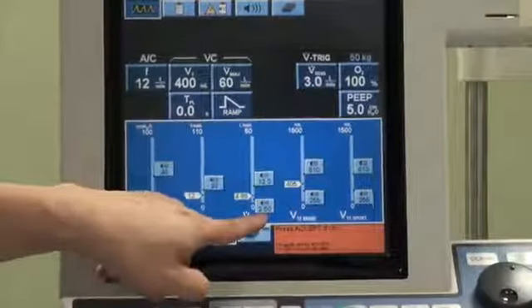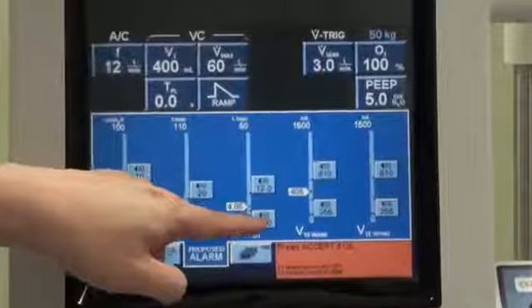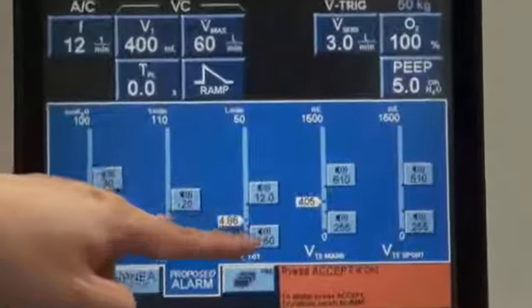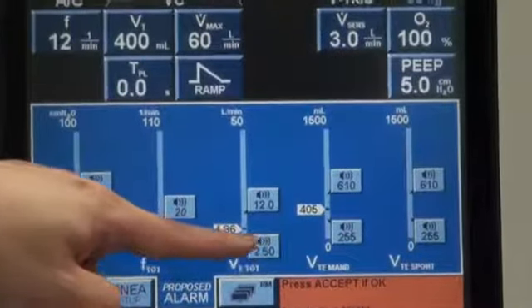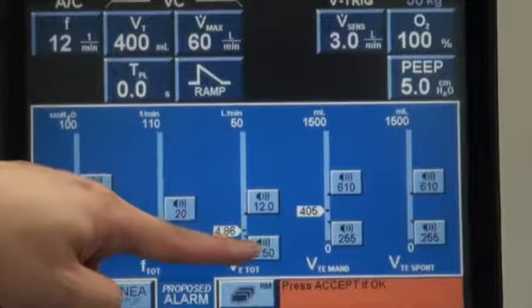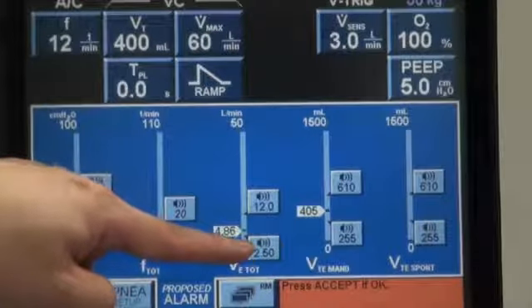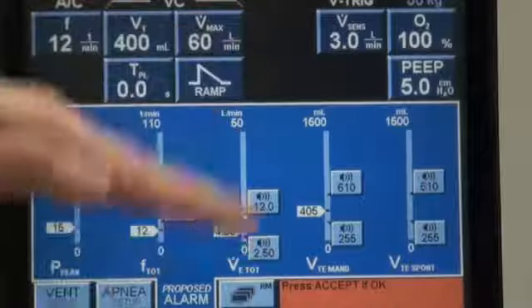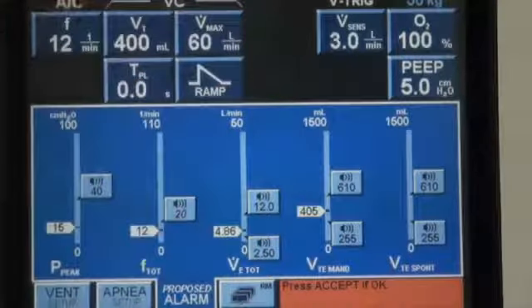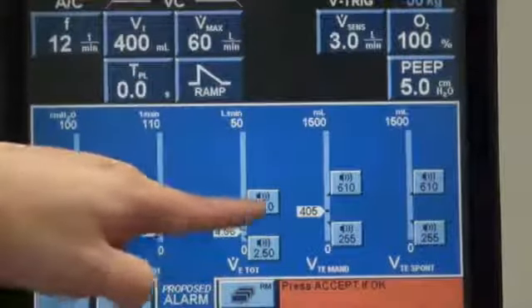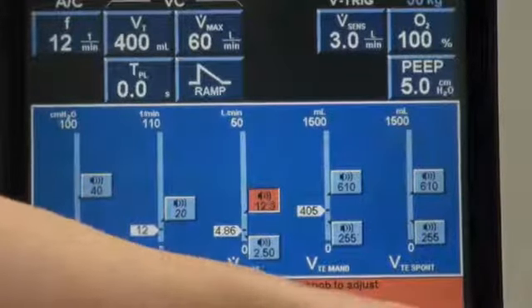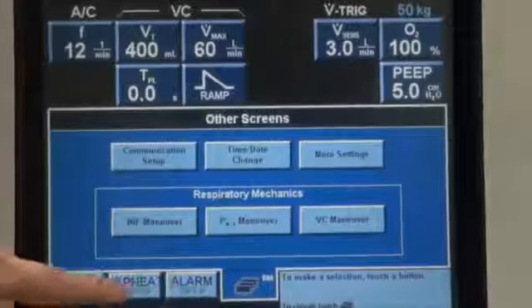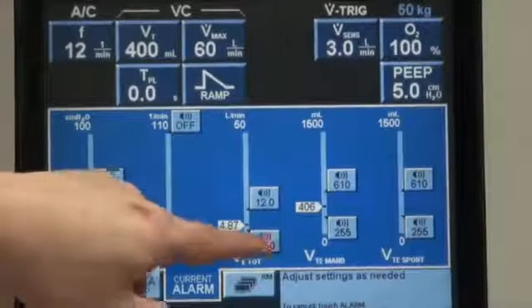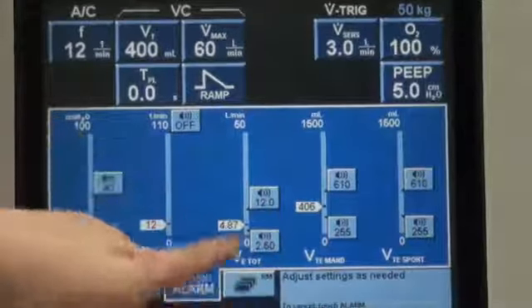The next button is actually the minute ventilation. As I said, the average minute ventilation for a patient at rest is about 5 to 8 liters per minute. How I usually set the alarm is to have a buffer of around 10% either above or below, and that will alert us when the minute ventilation exceeds the limit that I set, or goes below the limit that I have set.